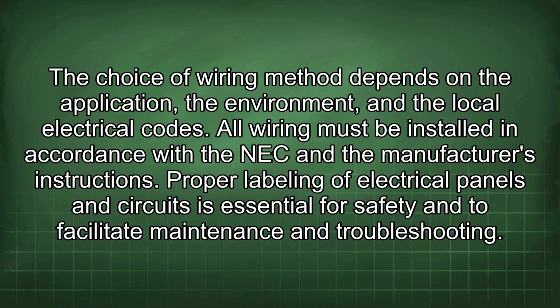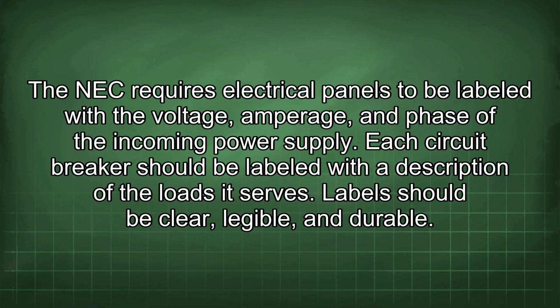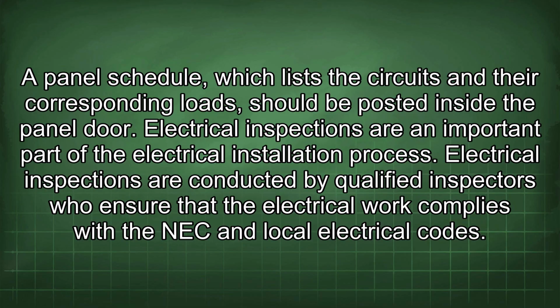Proper labeling of electrical panels and circuits is essential for safety and to facilitate maintenance and troubleshooting. The NEC requires electrical panels to be labeled with the voltage, amperage, and phase of the incoming power supply. Each circuit breaker should be labeled with a description of the loads it serves. Labels should be clear, legible, and durable. A panel schedule, which lists the circuits and their corresponding loads, should be posted inside the panel door.